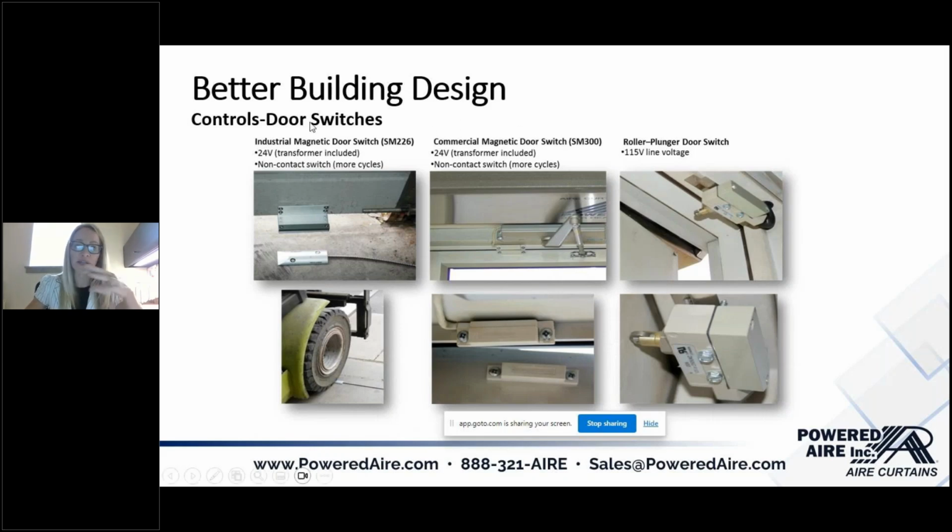I typically only deal with these magnetic door switches. They're a little bit more money up front, maybe $75, because they're low voltage. So we have to put a low voltage transformer in the air curtain, but the end result is so much better. Picture on the left is our industrial SM226 door switch. And then in the center is more of the commercial version. Aside from this, there's so many other options for magnetic door switches. There's little wobble switches. We can even do ones that recess into door frames. So please, if you're specifying an air curtain, please specify a magnetic door switch. The end user is going to be so much happier with the final result.